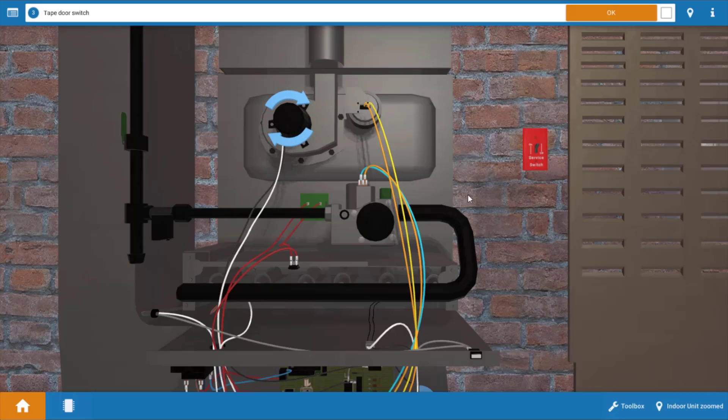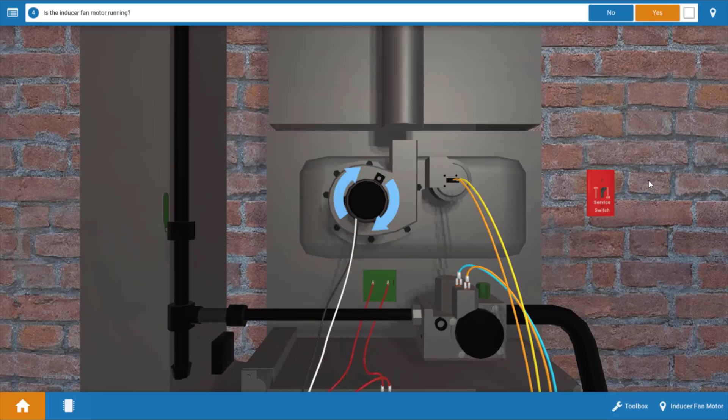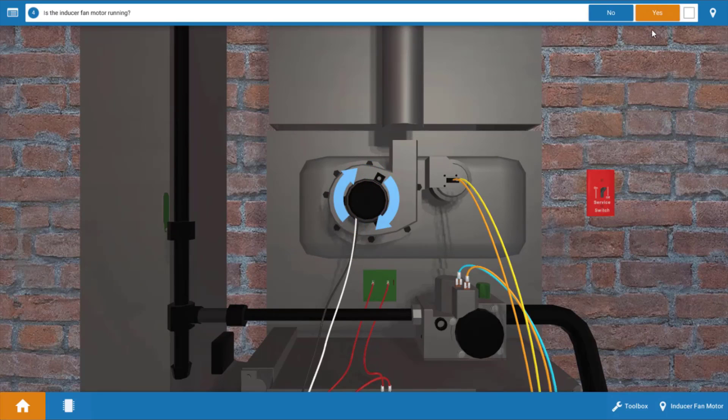Now we see that our inducer is running and that's the first component that should come on within the sequence of operations. So yeah our inducer is running.